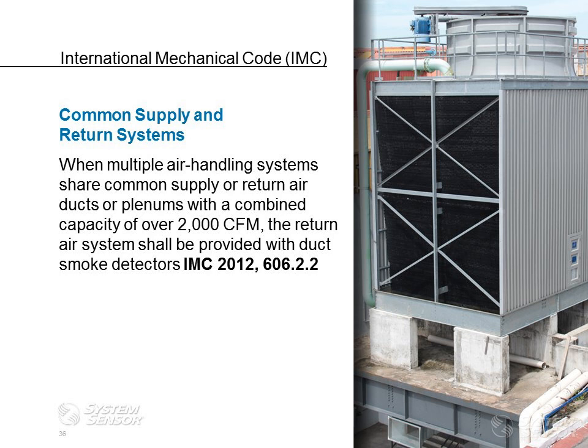Common supply and return systems for the IMC. When multiple air handling systems share common supply or return air ducts or plenums with a combined capacity over 2,000 CFM, the return air system shall be provided with duct smoke detectors. Some of you may be asking, well, why is that important? That's basically what we said in the previous slide.